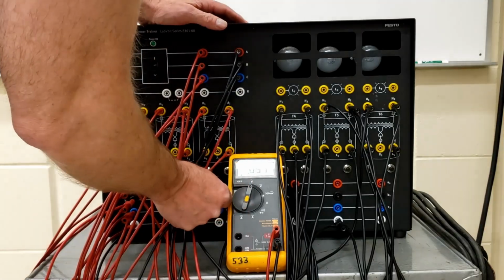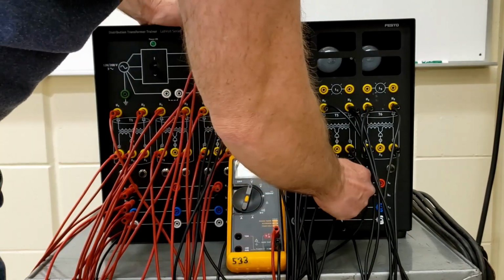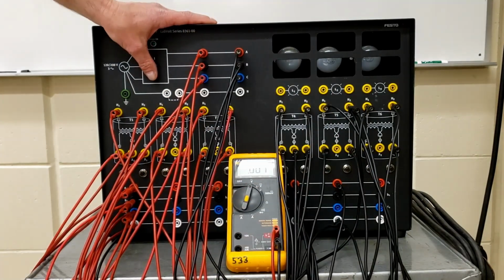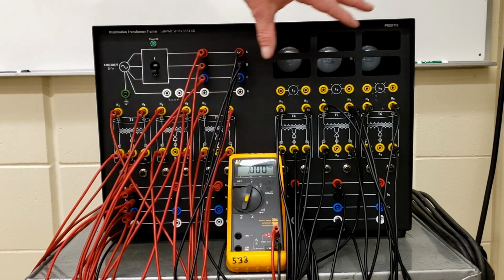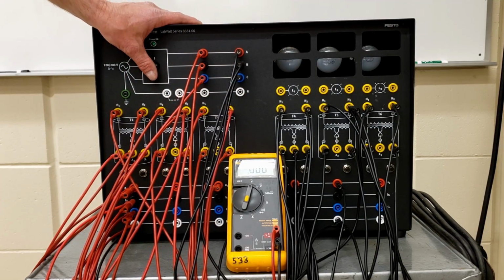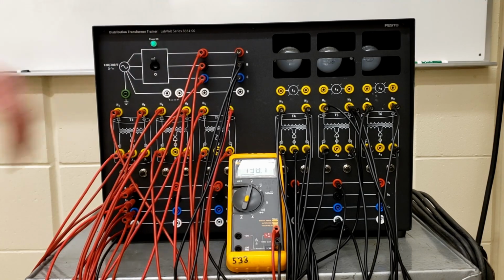So A1 and A2: those transformers have a 30 degree phase shift on the first one and 210 degrees on the other. So there should be a voltage difference between those two buses, and we're seeing 138 volts.